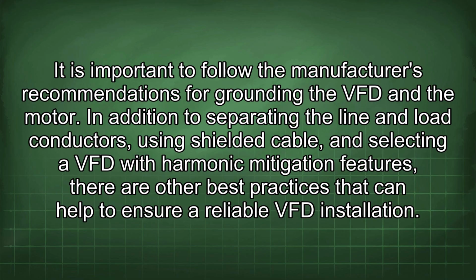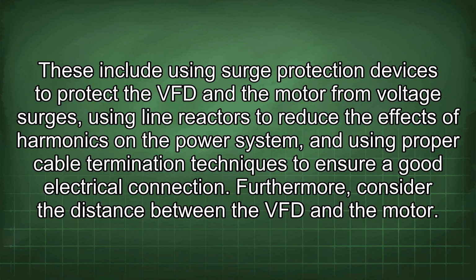In addition to separating the line and load conductors, using shielded cable, and selecting a VFD with harmonic mitigation features, there are other best practices that can help to ensure a reliable VFD installation. These include using surge protection devices to protect the VFD and the motor from voltage surges, using line reactors to reduce the effects of harmonics on the power system, and using proper cable termination techniques to ensure a good electrical connection. Furthermore, consider the distance between the VFD and the motor.